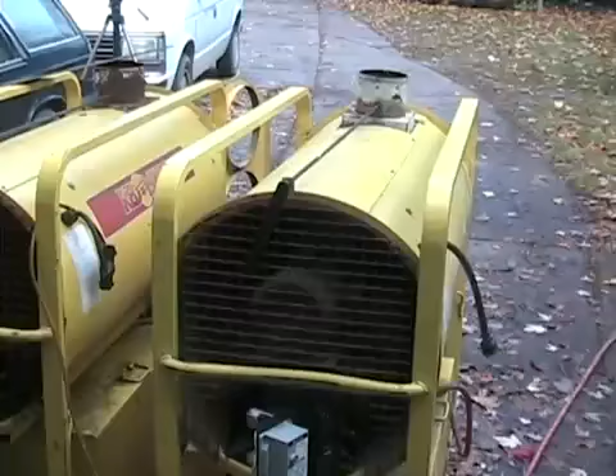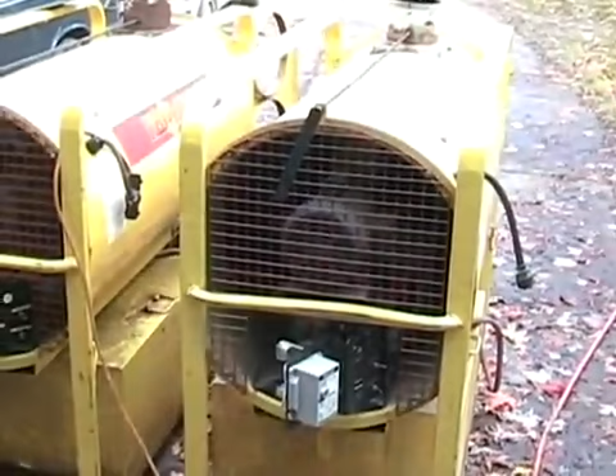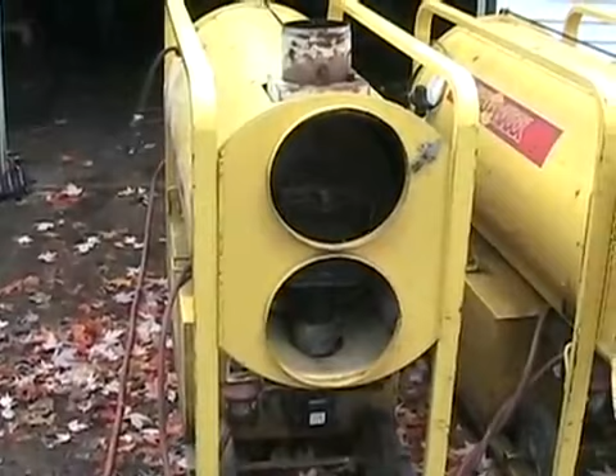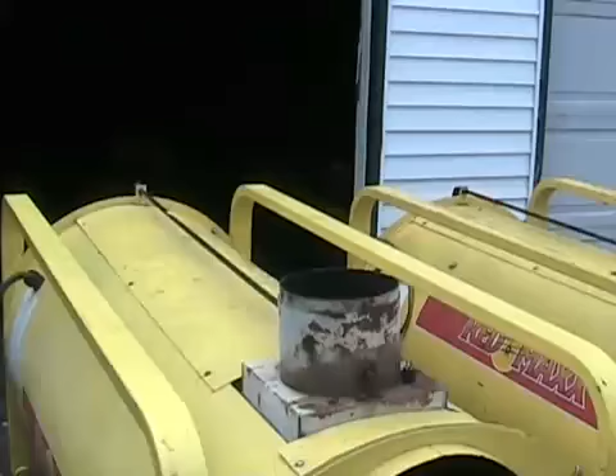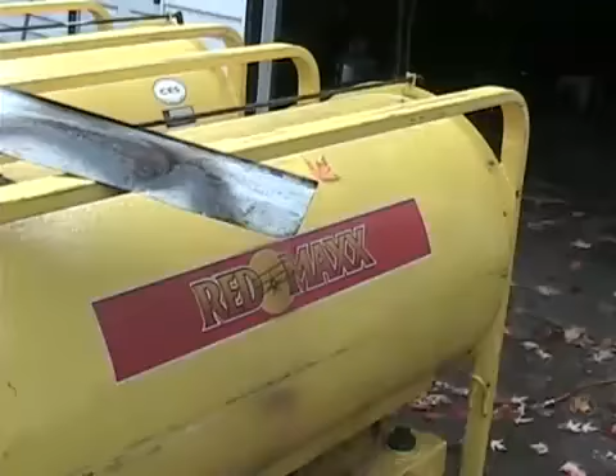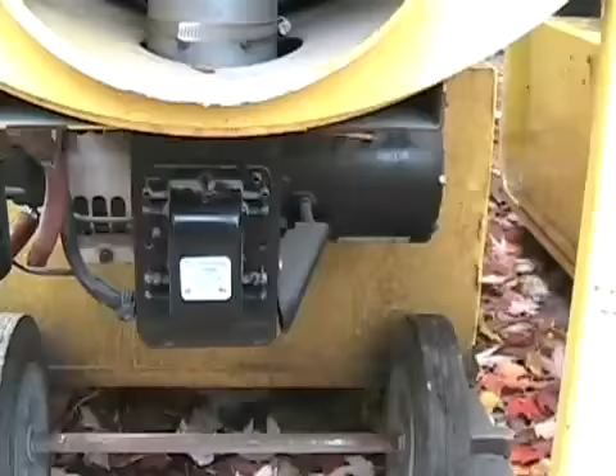They've got a combustion chamber in that big tube and a heat exchanger and a powerful fan motor to blow air through there. Something like the way your furnace works, pretty much exactly the same but just a different shape. And hot air blows out that end so you can heat up a shop or an apartment building or something you're working on in building, or a giant tent. The exhaust goes out the top, of course. So at the back end of the unit, just like your oil furnace at the bottom, you've got a 1/4 horsepower electric AC motor. Then in the center of the unit, you've got that rectangular box there, and that's your high voltage supply. It's a transformer. It makes anywhere from 10 to 15,000 volts to ignite the fuel.